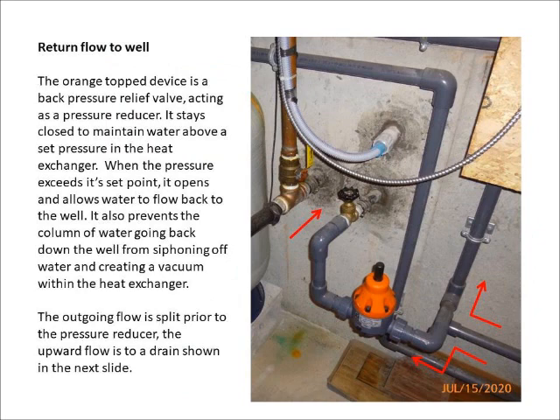This view shows the return flow to the well through the gray PVC pipes with the red arrows. The orange top device is a back pressure relief valve acting as a pressure reducer. It stays closed to maintain water above a certain pressure in the heat exchanger. When the pressure exceeds its set point, it opens and allows water to flow back to the well.